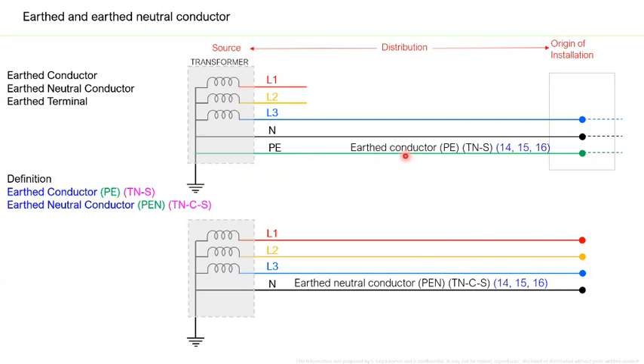Earthed conductor is a TN-S system. The fifth conductor in the distribution is the earthed conductor. Regulations 14, 15, and 16 say it is the responsibility of the utility company to provide an earthed conductor, meaning TN-S, or earthed neutral conductor, which is a TN-C-S network. In a TN-C-S network, the provision is for making the earthed terminal. It's not an earth terminal, it's an earthed terminal. Earthed terminal means a terminal, here where I'm moving the cursor, which is connected to the neutral of the source. So for this whole power supply, earth is the point at which one of the live current carrying conductors is connected to earth.